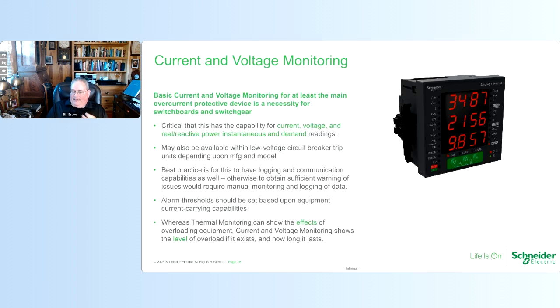Second, basic current and voltage monitoring for at least the main overcurrent protective device is a necessity for switchboards and switchgear. And because the heating effect over time is what's critical, again, heat is the enemy of insulation, both instantaneous and demand reading capabilities are required. So this can be a separate device, like we've shown on the slide here, or in some cases can be built into things like low voltage circuit breaker trip units or protective relays for medium voltage equipment. In order for this to be most efficient, logging and communication capabilities are definitely recommended. Otherwise, you would end up sending someone to the equipment periodically to take spot readings, and this is of limited value. That's really not continuous monitoring in the definition that we're using here.